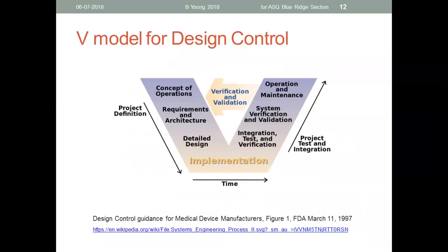You don't want to wait until your product is designed before you do risk management. You will want to do risk management as early as possible, even at the concept stage of product development. There are risk tools available to start looking at areas that may pose risks in your product performance or product safety that should be applied.